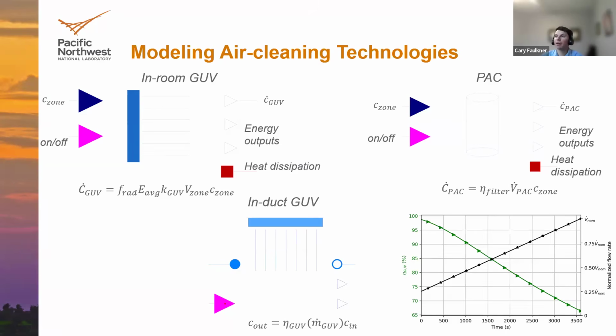phenomenon using a dose relationship that describes the amount of time that the pathogens spent in that irradiated space and how much dose they receive from the system, connected with the airflow rate, which connects with the amount of time that the air is spending in that space. So this plot on the right shows in black how, if you linearly increase the airflow rate from 25% of the nominal flow rate up to 100% of the nominal flow rate, the estimated inactivation efficiency decreases from close to 100% to closer to 65%. And this is described by an exponential relationship. And then we, of course, have our flow in and flow out, energy outputs, and the on-off signal for these devices.